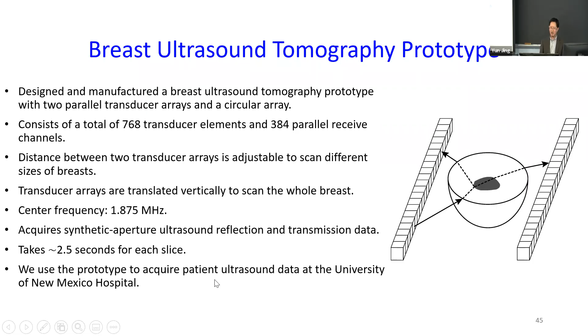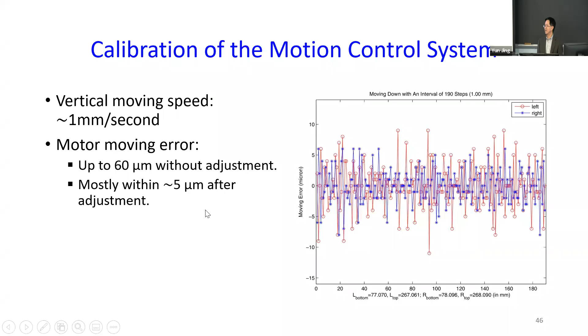The first thing is I need to calibrate this machine to make sure it moves vertically and in parallel without much error, so we do some adjustment automatically. The moving speed is about 1 millimeter per second. Without adjustment, the motor can have an error of 60 microns. After adjustment, shown here for both the left and right transducer arrays, the error is less than about 5 microns, within a 5 micron range, for most of it. So that's accurate enough.